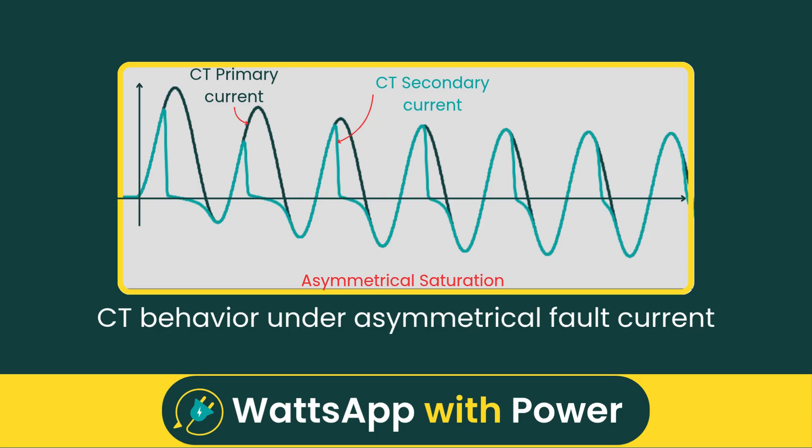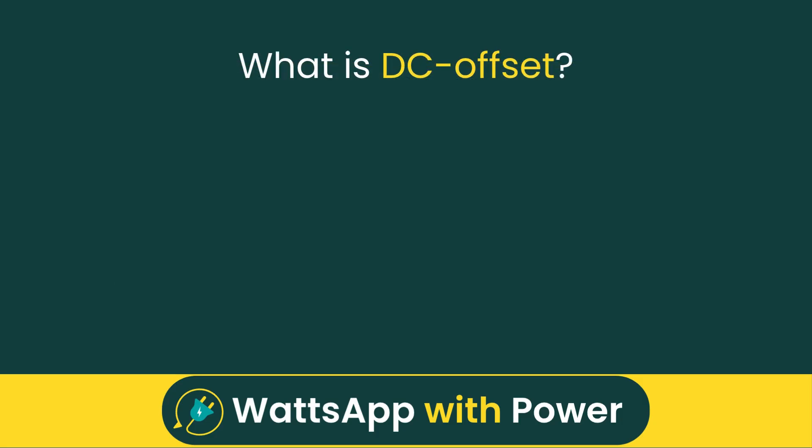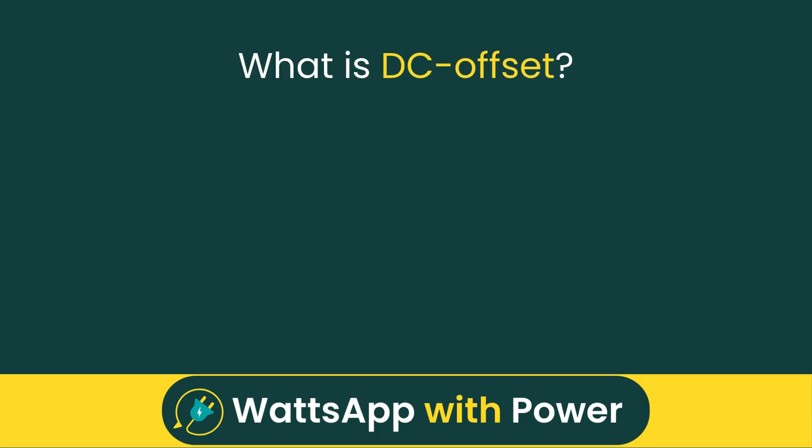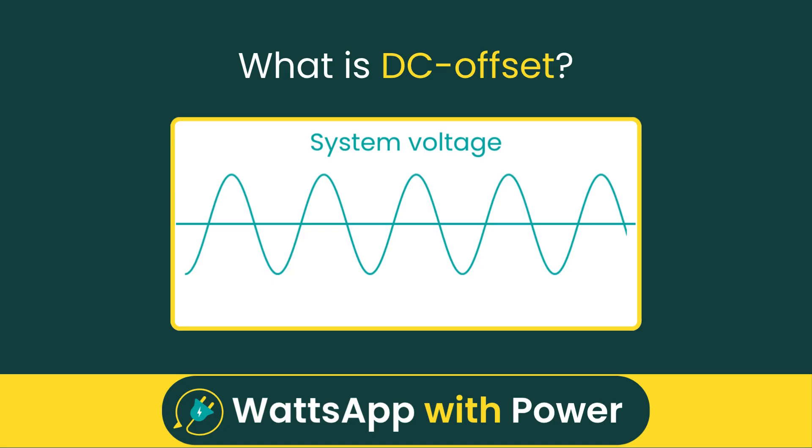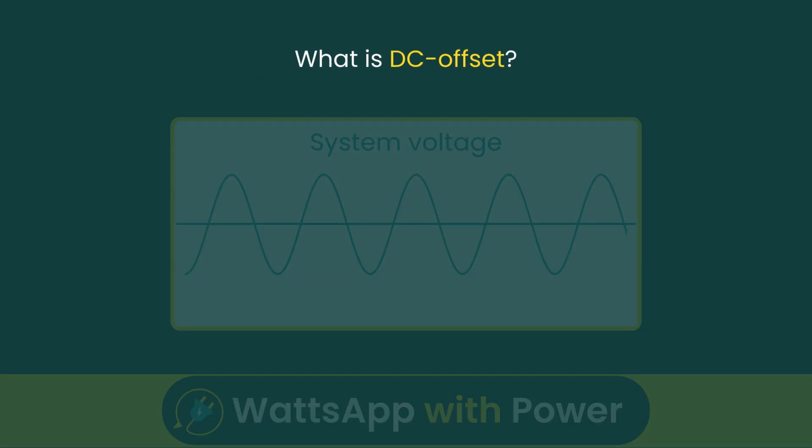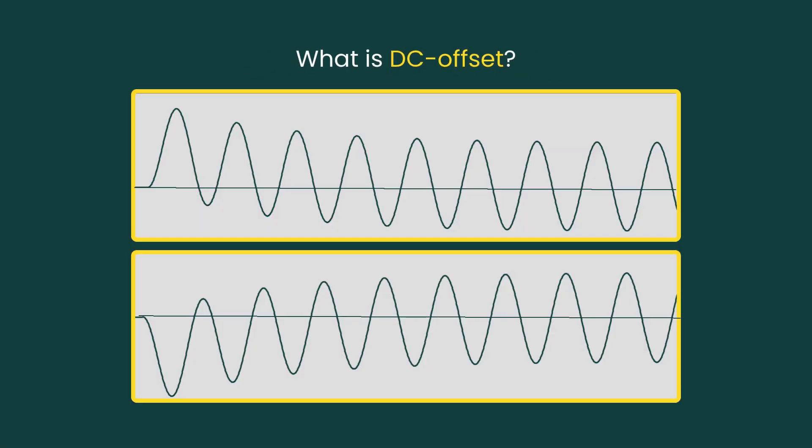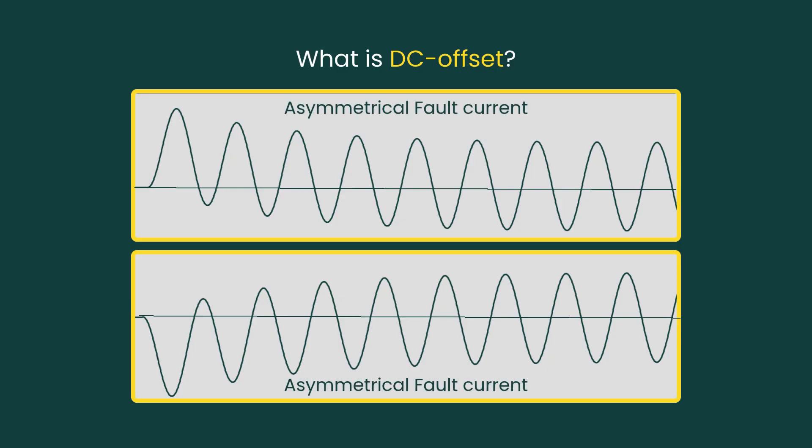Before we dive deeper, let's first understand what is DC offset. DC offset occurs when a fault happens at a point other than the voltage peak, for example, exactly at the voltage zero crossing, especially when the network impedance is mainly inductive. This causes the current waveform to shift upward or downward, resulting in asymmetrical fault current.